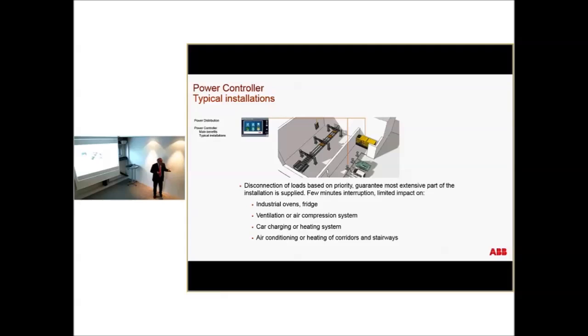The first load disconnected is the first load, the last to connect. So the last load you disconnect is probably the highest priority one and is the first that reconnects. Basically, this is a very useful device because it calculates the average of the energy every 15 minutes. If you have a motor startup or something like that, some high consumption that is essential, it is not touched and not disconnected. But if you have something that can be disconnected, you can measure the energy over a period of time and do it.